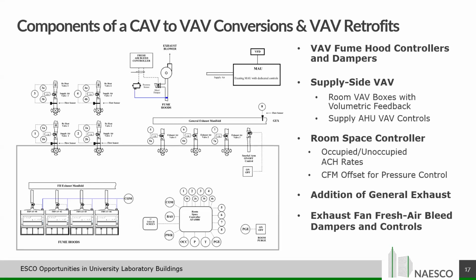Now, what are the actual components of a CAV to VAV conversion, or a VAV retrofit for that matter? So this diagram here gives us something to talk about, what's actually physically involved with retrofitting a lab. Down in the left-hand corner here, we've got our fume hoods. And for each one of these fume hoods, if it was a constant air volume system, you need to add a damper or a venturi valve, and retrofit that in there with a controller, so you control your volume of exhaust to keep your face velocity where it needs to be across your sash opening at a variety of sash heights.